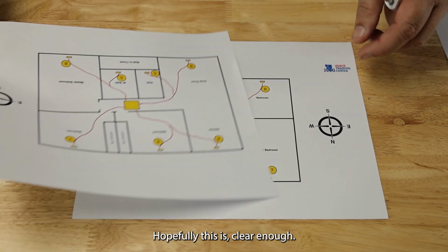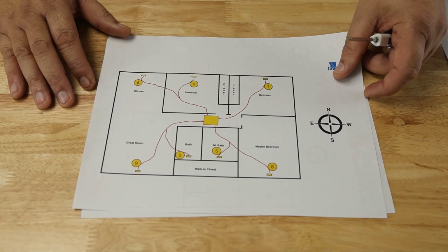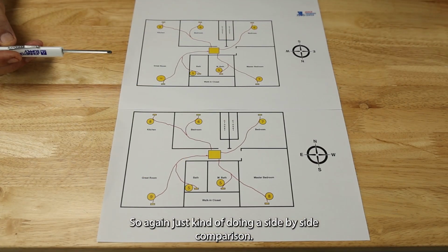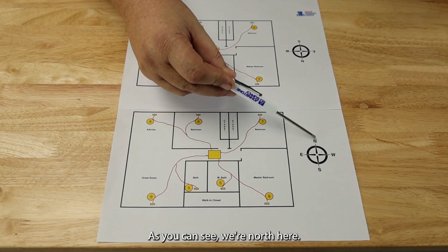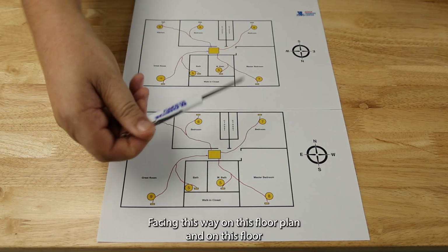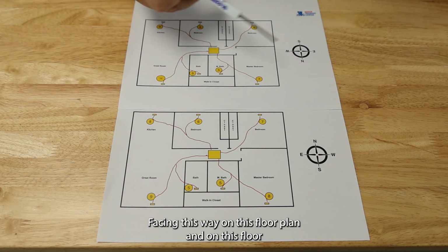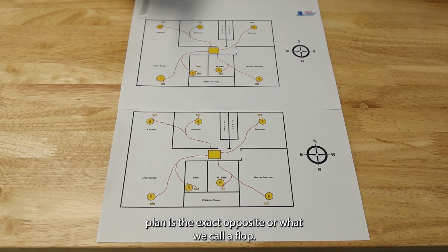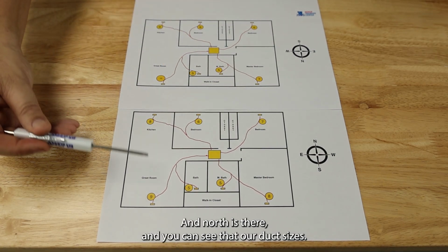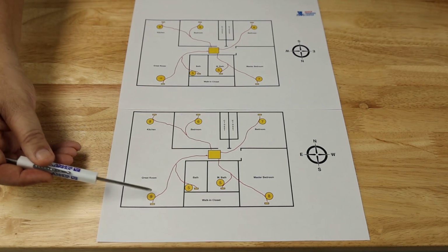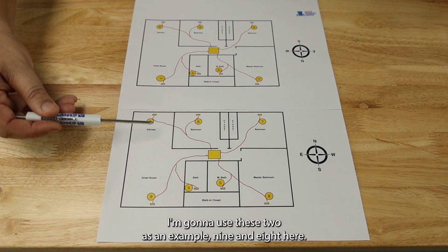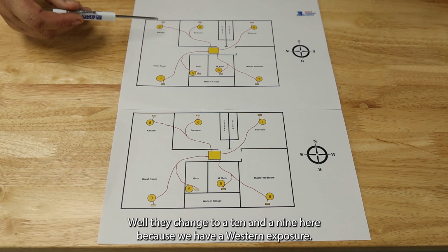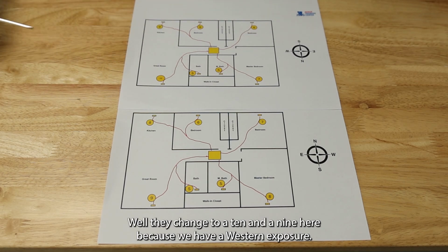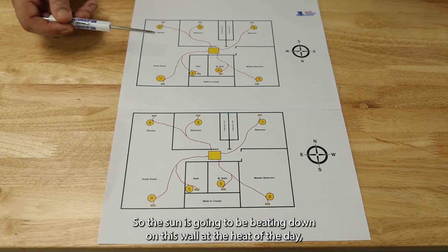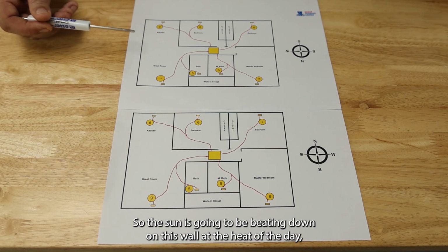Hopefully this is clear enough. All right, so again, just kind of doing a side-by-side comparison. As you can see, we're north here, facing this way on this floor plan, and on this floor plan it's the exact opposite, or what we call a flop, and north is there. And you can see that our duct sizes, I'm going to use these two as an example, 9 and 8 here. Well, they changed to a 10 and a 9 here because we have a western exposure, so the sun is going to be beating down on this wall at the heat of the day, right?